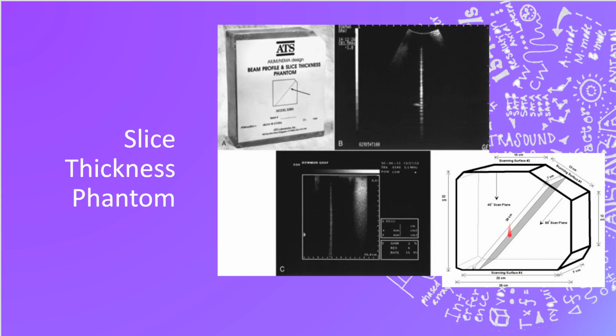You scan with the surface that is parallel with the bar, and it will tell you different information about each one. So we can tell on this one up here that we are getting our slice thickness measured in this one. This image is being taken from the 45 degree scan plane. What's happening is that the beam is heading into the tissue, it's interacting with the bar, and what it's telling us is how much of that bar is being seen. So we can go in and measure from side to side on this image, and it would tell us that our slice thickness is actually 1 millimeter, 2 millimeters wide. That would be our elevational resolution that we are testing with this.